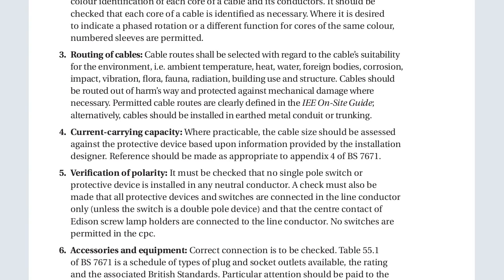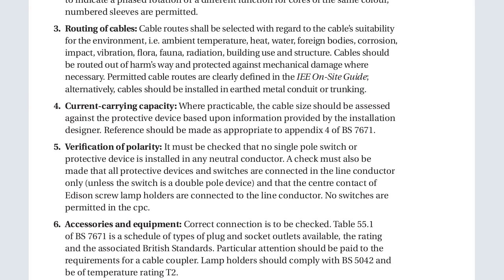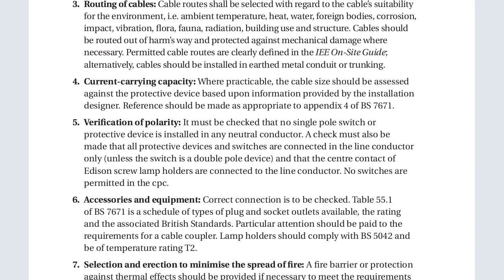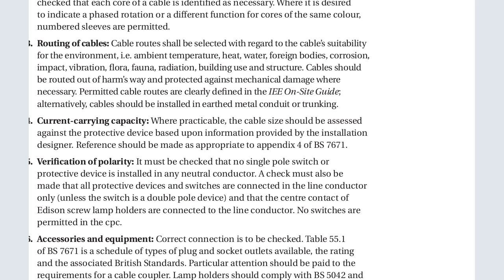Another one is the verification of polarity. It must be checked that no single pole switch or protective device is installed in any neutral conductor. That is very important. A check must also be made that all protective devices and switches are connected in the line conductor. What do you mean by line conductor? The line conductor is a live pole. Normally, a protective device is like a circuit breaker or a switch. What is the work of a switch? The work of a switch is to break the circuit, and you can only break the circuit on the live conductor.